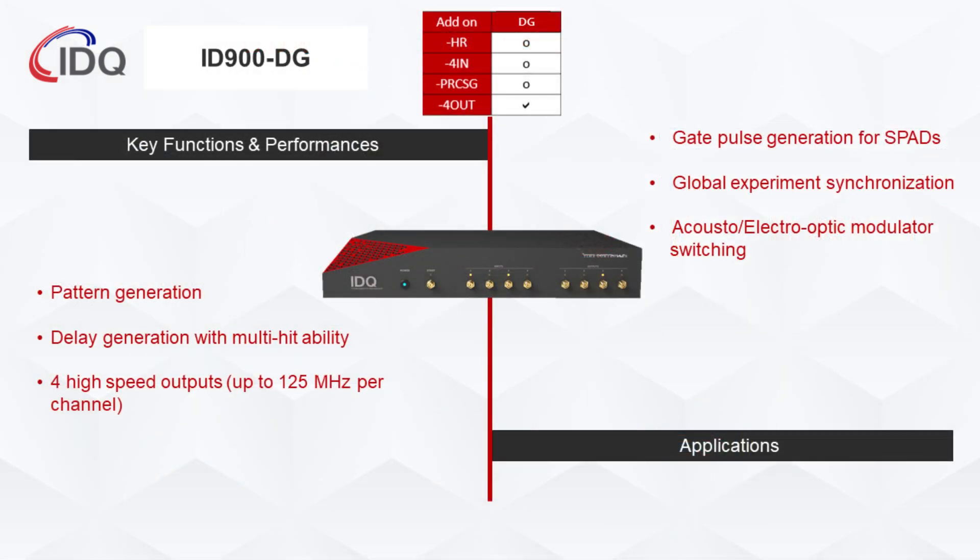Some users may prefer to use the ID900 solely as a function generator. Its four high-speed outputs are useful for global experiment synchronization, such as triggering your laser with defined pulses, while also generating gate pulses for gated SPADs such as the IDCube.